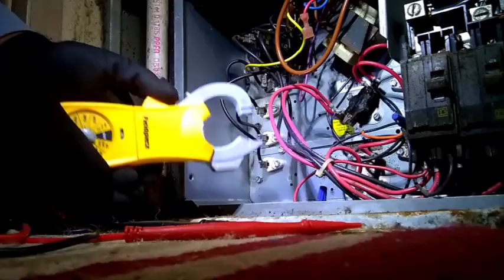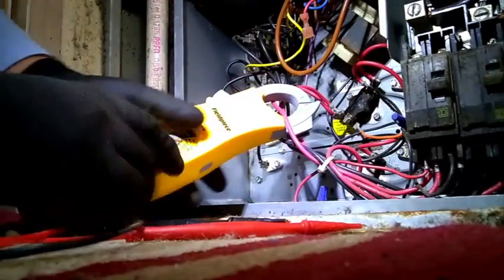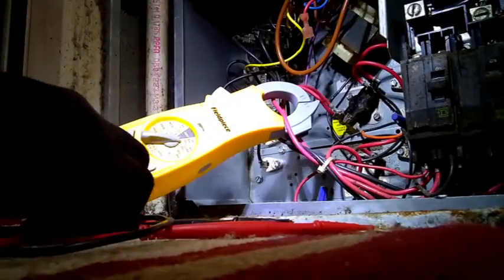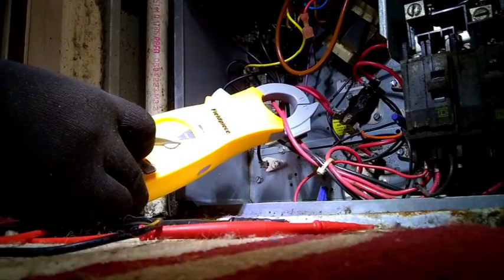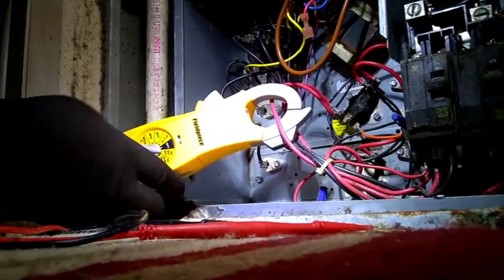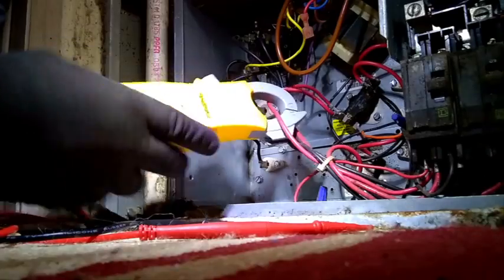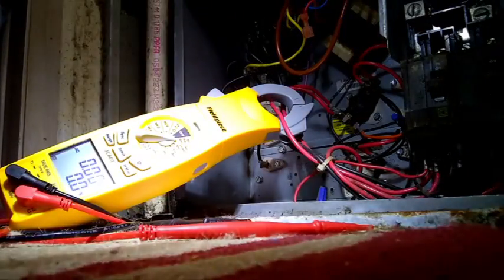The complaint was that the unit would turn on in heat, and it would take a long time for the heat to come on. So I've been looking at the sequencers because they're usually the prime suspects there. It could be the blower relay too, but I just replaced the blower relay a few months ago.